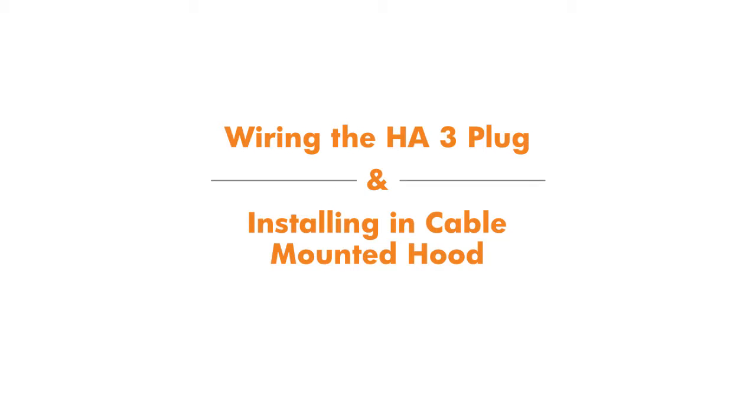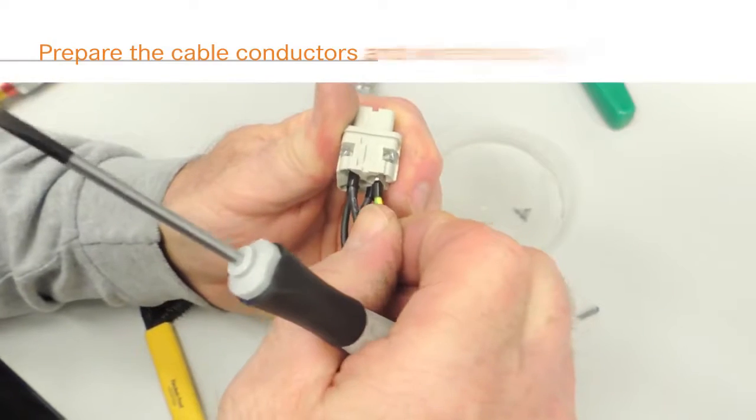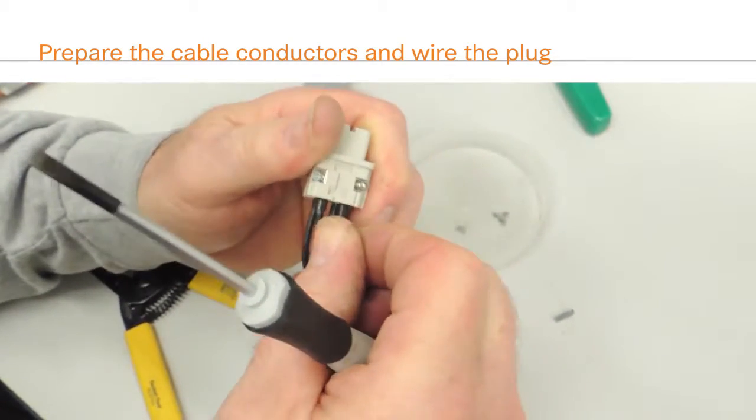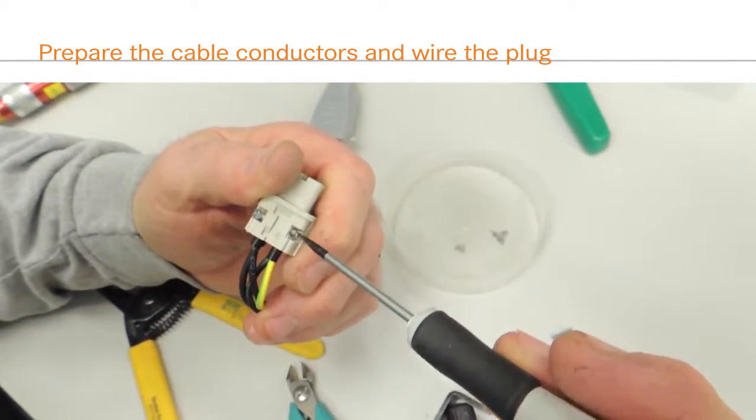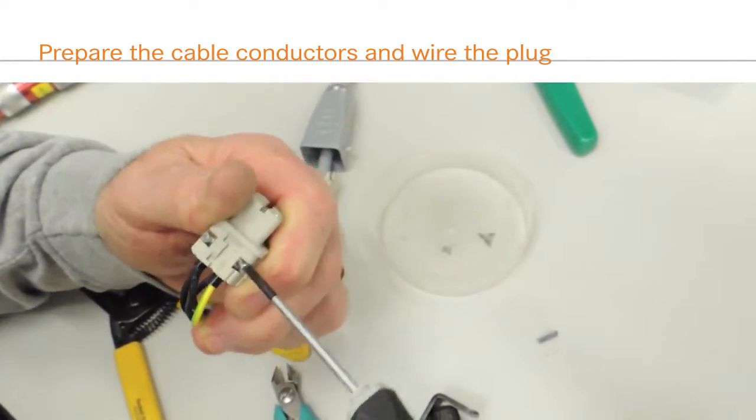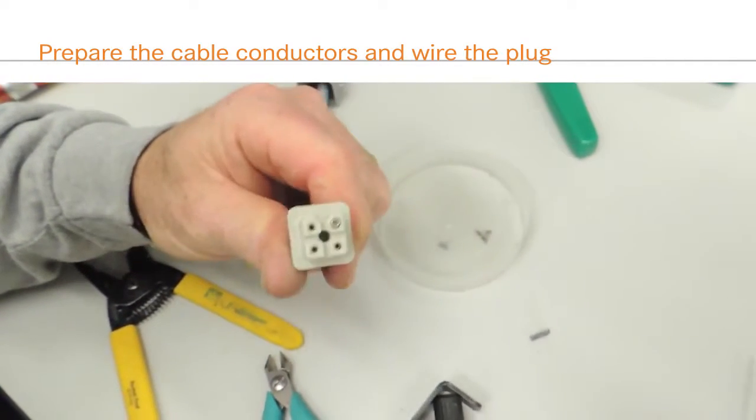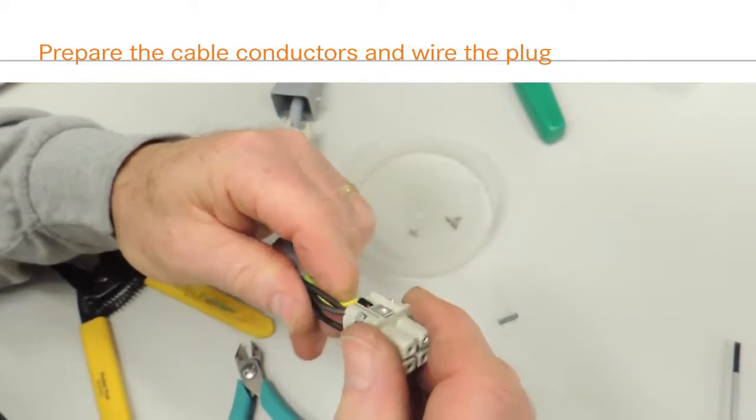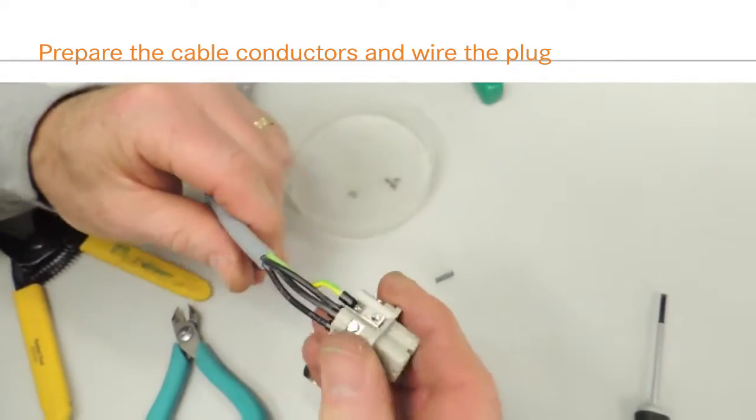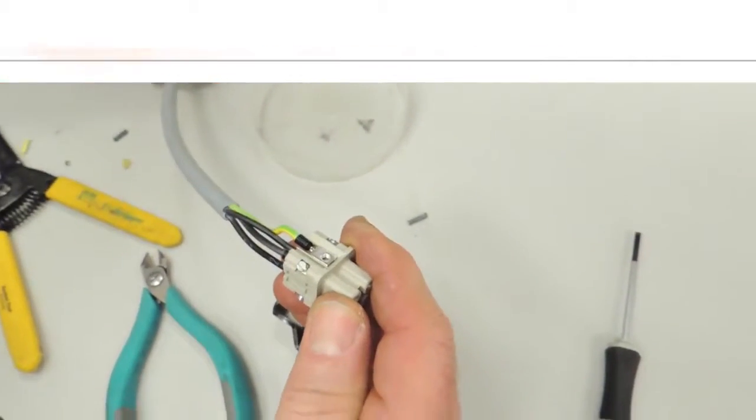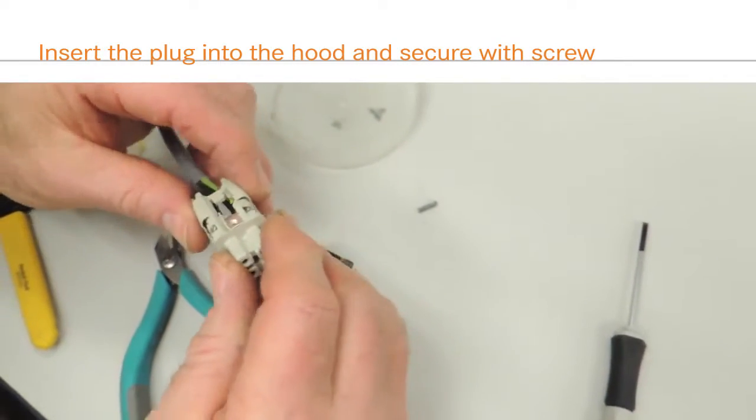Now we will wire the EPIC HA3 plug. Begin by sliding the EPIC HA3 hood on the cable. Next, prepare the cable as outlined previously. Strip the conductors, affix the wire ferrules, and insert the conductors into the HA insert. Once the insert is wired, slide the terminal cover over the terminal screws, install the insert into the hood, and secure with the screw.